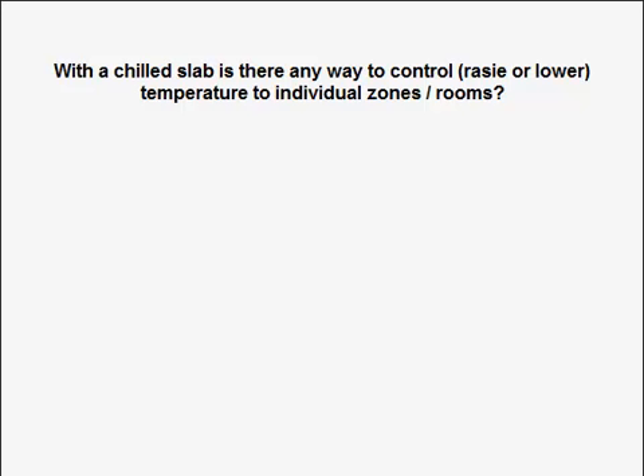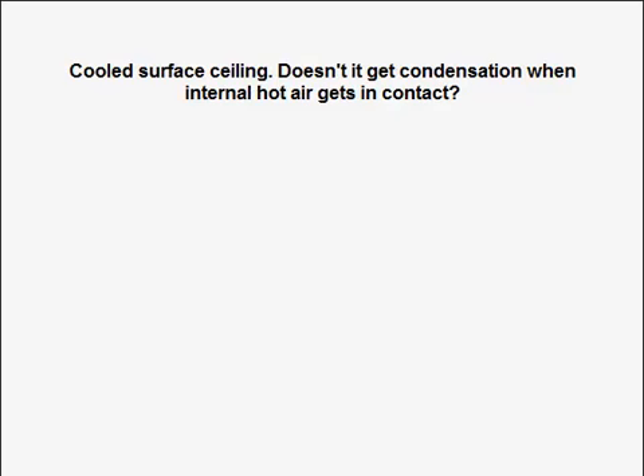Another technical question here from Sangmok Kim: cooled surface ceiling may seem quite simplistic — doesn't it get condensation when internal air comes into contact with it? No, you design it so that can't happen. The lowest temperature you can supply water at to prevent condensation forming is about 14 degrees. If you went any lower, you'd run the risk of condensation forming under certain conditions. So that's the limit, and no one really goes below that level.